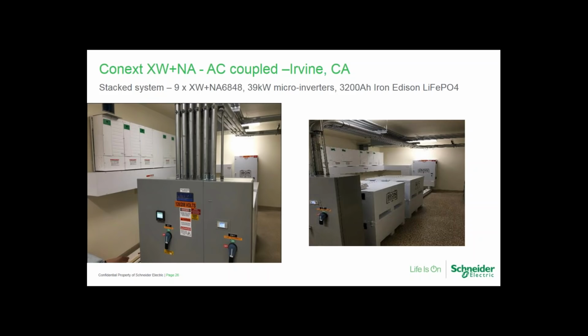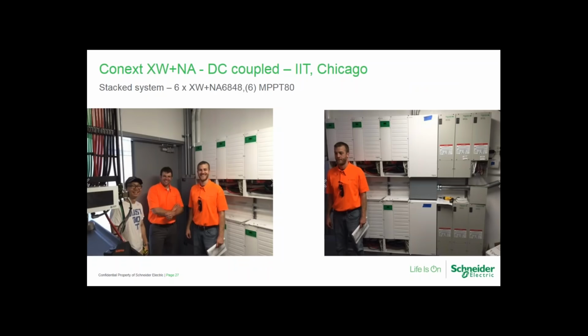Here we see the DC coupled system at Institute of Technology in Chicago. And this system actually provides backup for a gymnasium and their lighting in the gymnasium. So we've got 3-phase, 2 inverters per phase, 120/208 and 6 MPPT 80 high voltage charge controllers.